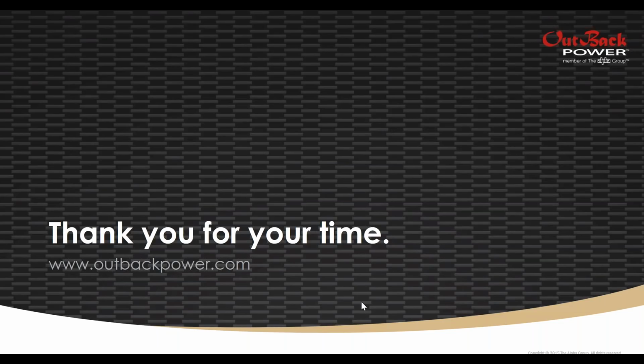Terry asked if we get a wiring diagram for the BOSS box with all breaker sizes shown. I know there's a wiring diagram for the BOSS. That's in the quick start guide. I don't remember for sure if the breaker sizes are labeled on that or not. I will have to check, Terry, and get back to you on that. The simple rule of thumb is that it's a 125 amp breaker on the battery, and it's 60 amps on all 3 ACs. And then the PV switch, I guess, would be a little different. So let me look into that and I'll get back to you.